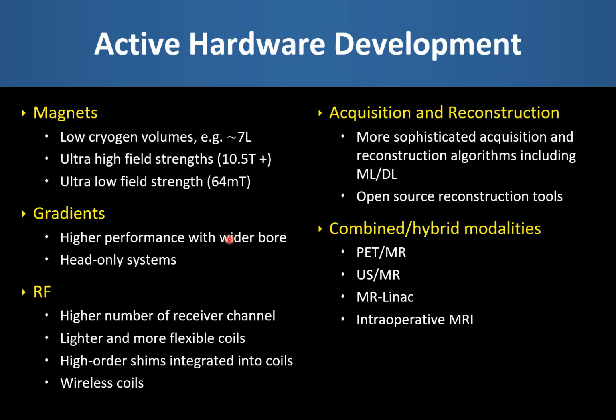In terms of gradients, vendors are working on providing higher performance gradients with wider bore scanners. Since the power required to drive a gradient coil scales with the fifth power of its radius, these energy requirements can be quite substantial. One way to obtain higher performance imaging, but just for the brain, is through the development of head-only magnets and head-only gradient coils. By virtue of their much smaller radius, they can achieve extremely high gradient performance, albeit only over a limited field of view.